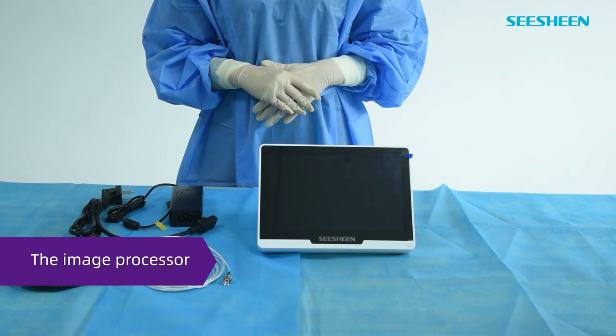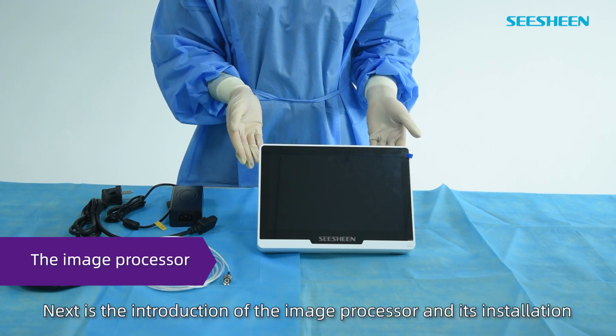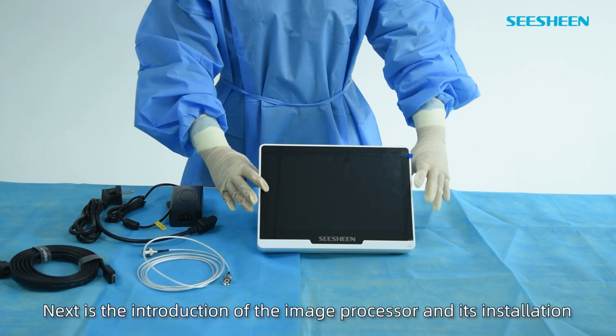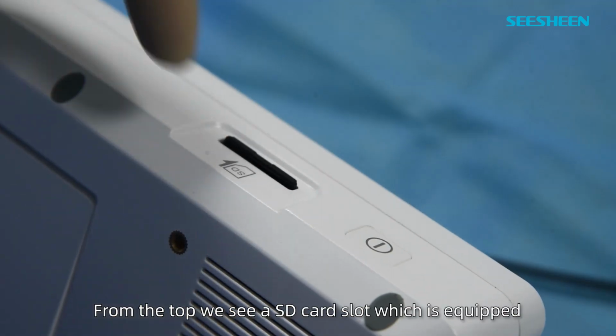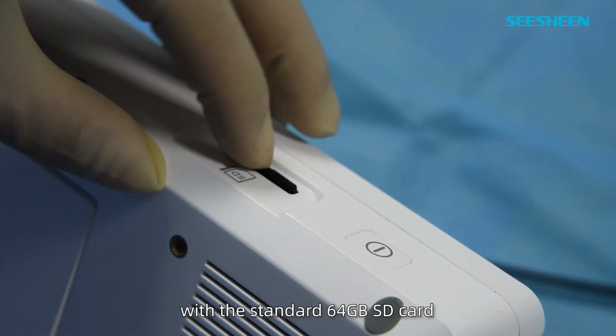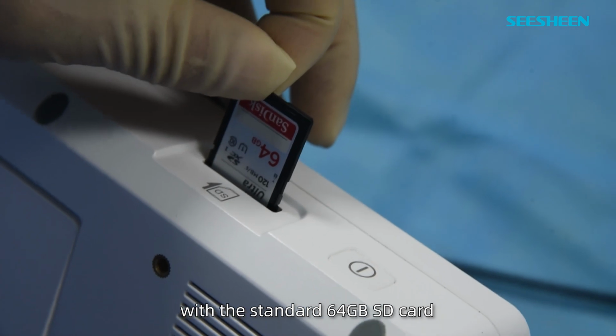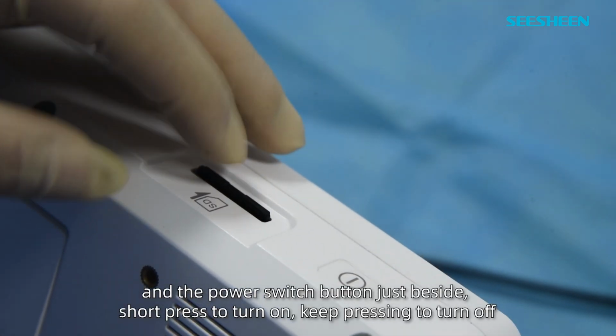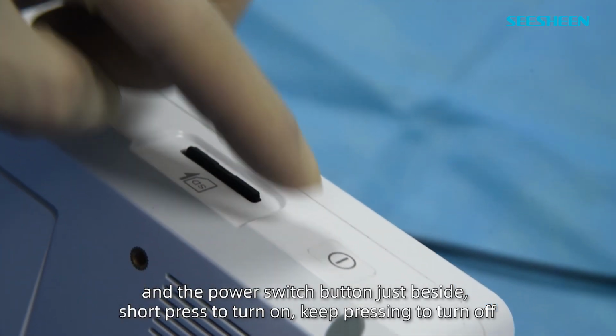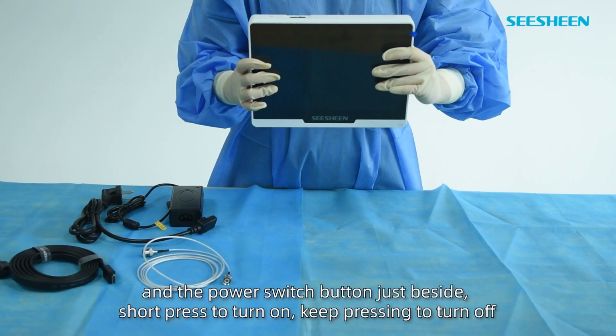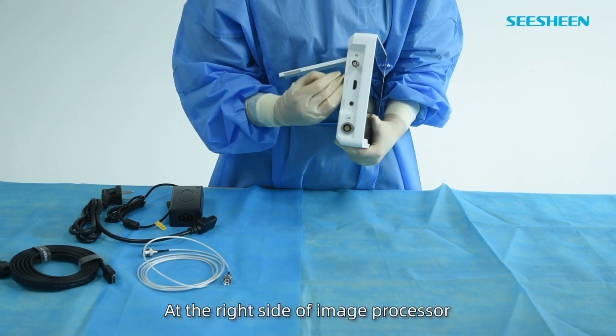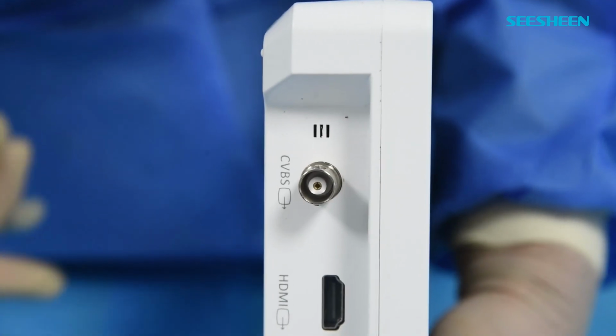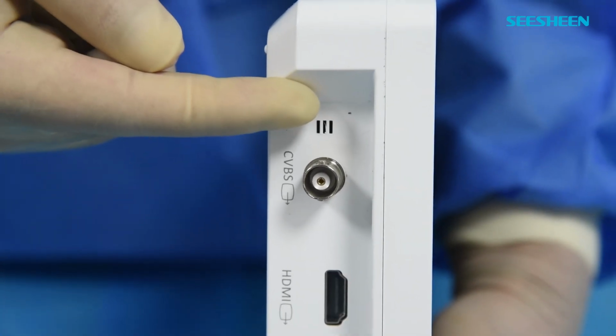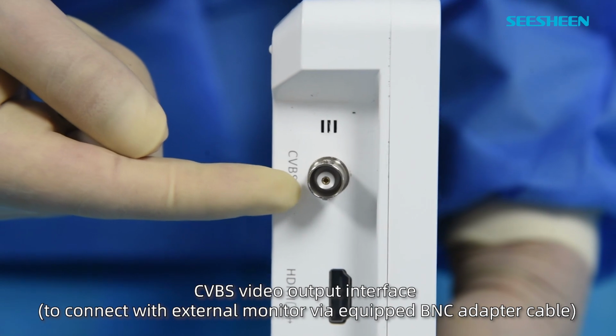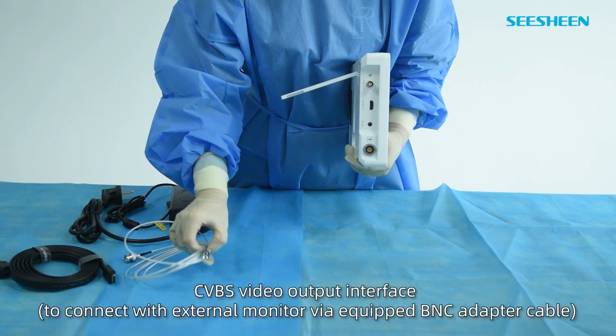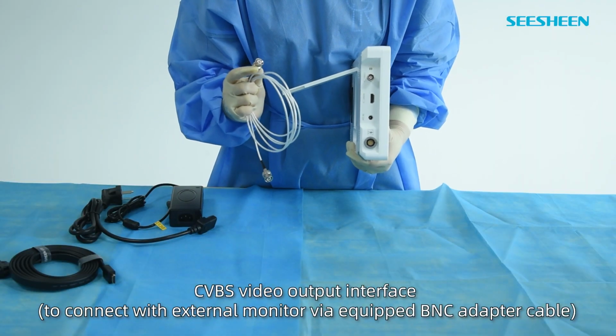The image processor. Next is the introduction of the image processor and its installation. From the top we see a SD card slot which is equipped with the standard 64GB SD card. And the power switch button just beside, short press to turn on, keep pressing to turn off. At the right side of image processor, there are microphone, CVBS video output interface, to connect with external monitor via equipped BNC adapter cable.